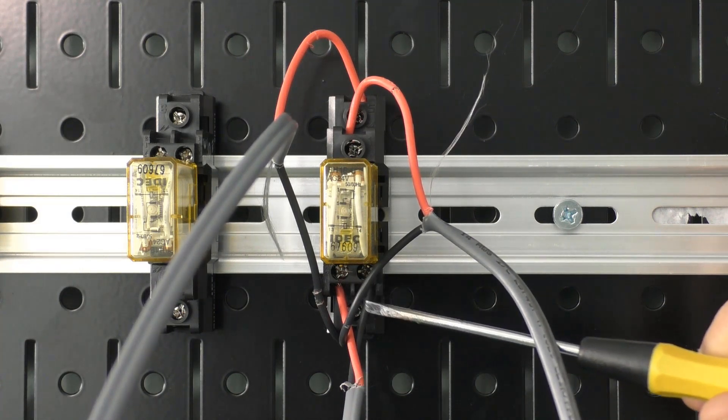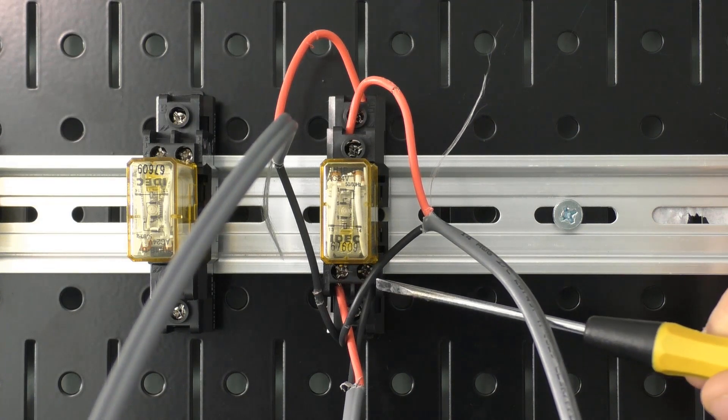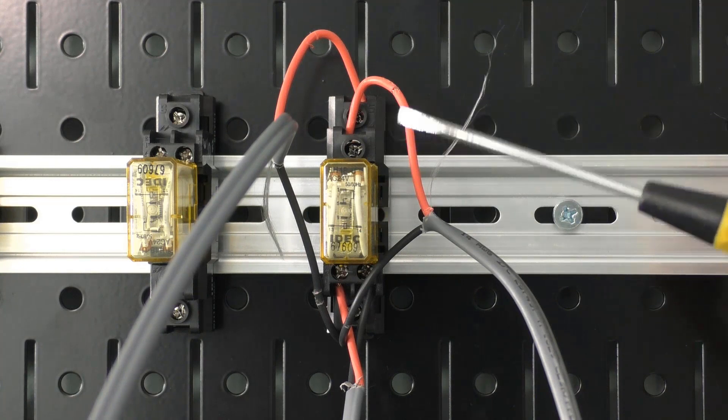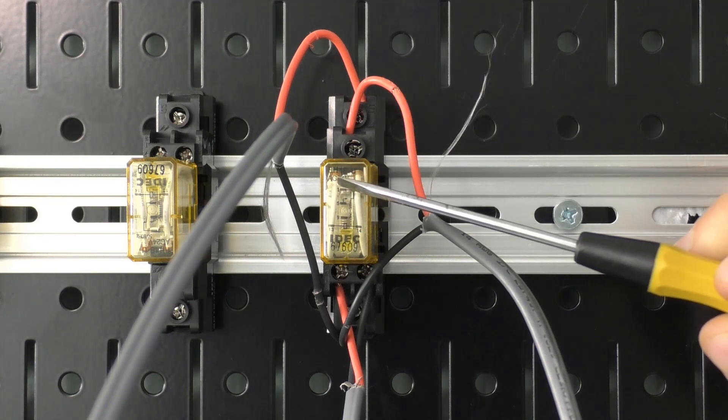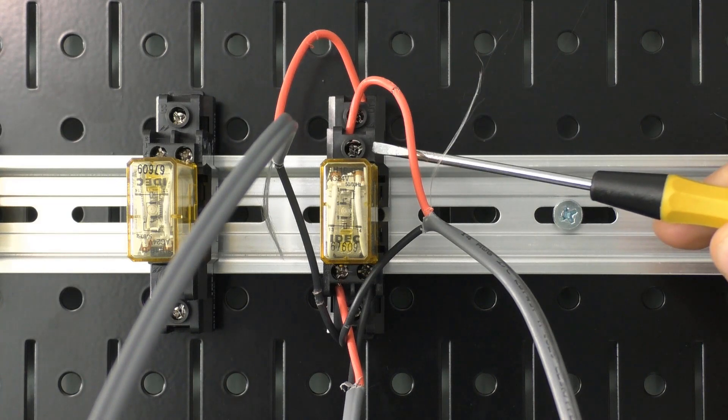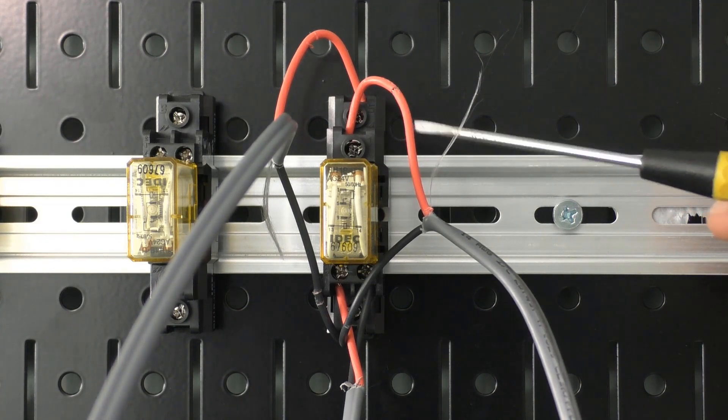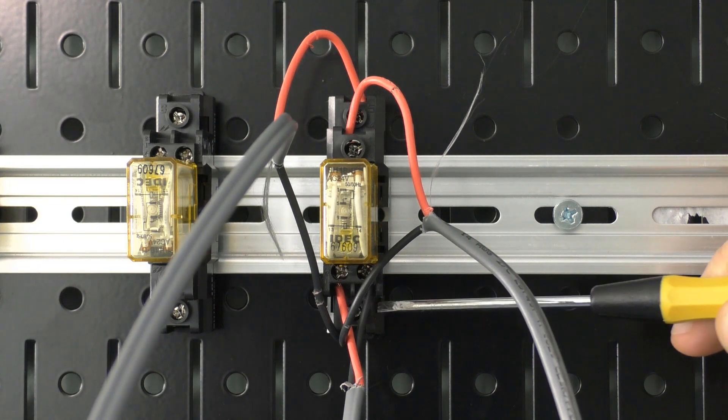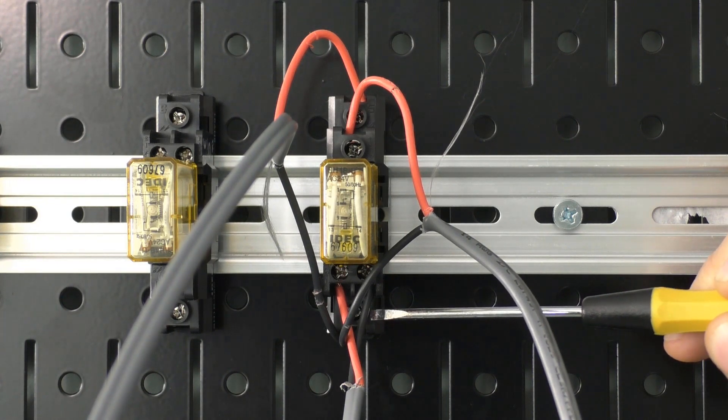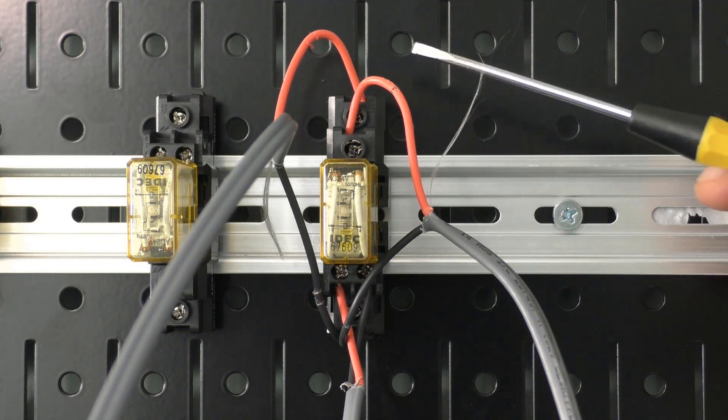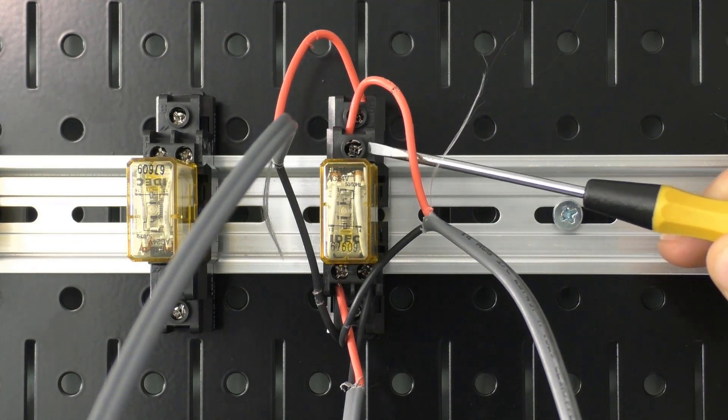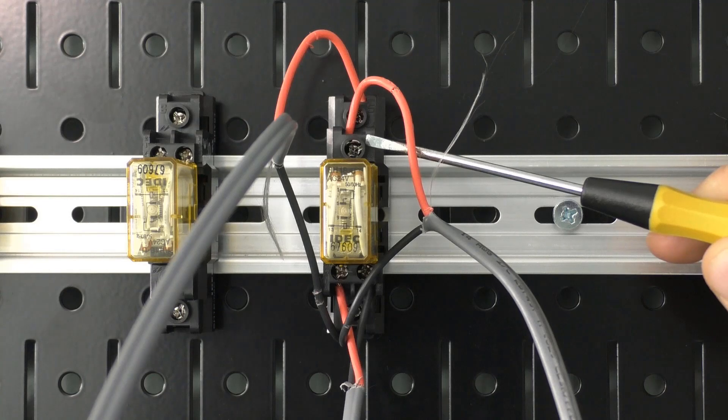If I were to meter this it would be 24 volts and it's energizing the coil. Now our normally open circuit is one to nine and we can see one right here with our entering wire and nine right here which is our leaving wire. Our leaving wire is always going to be at the bottom and the top is going to be for our different contacts.